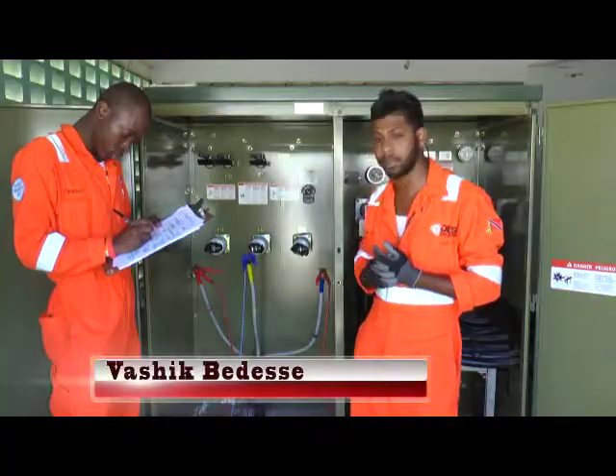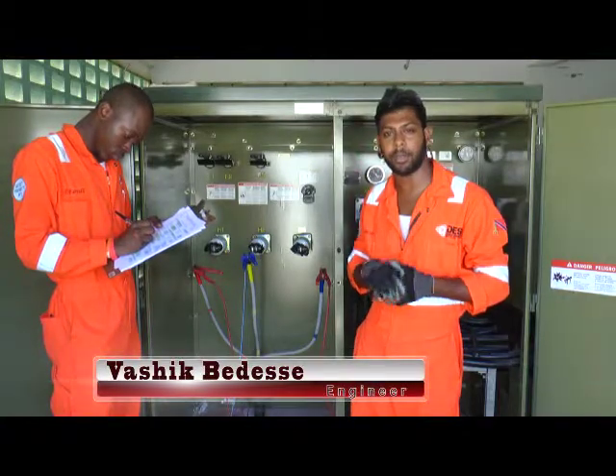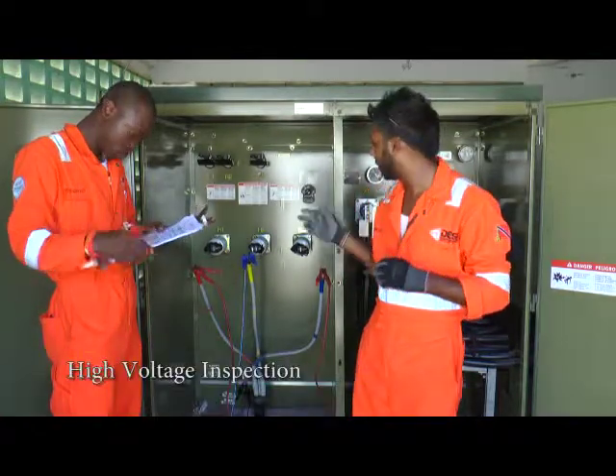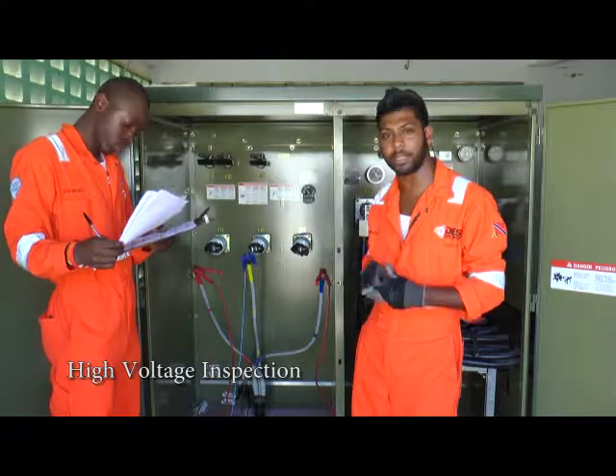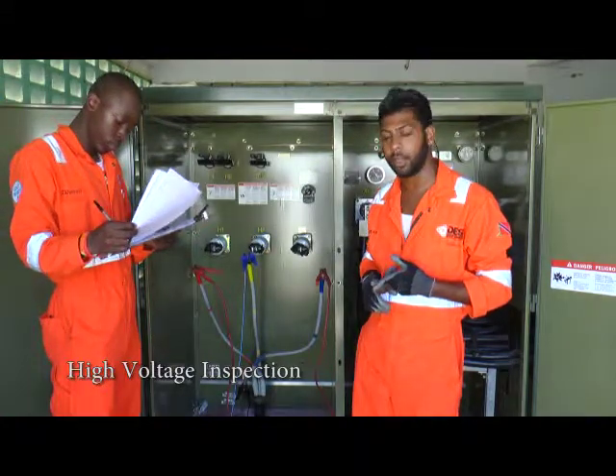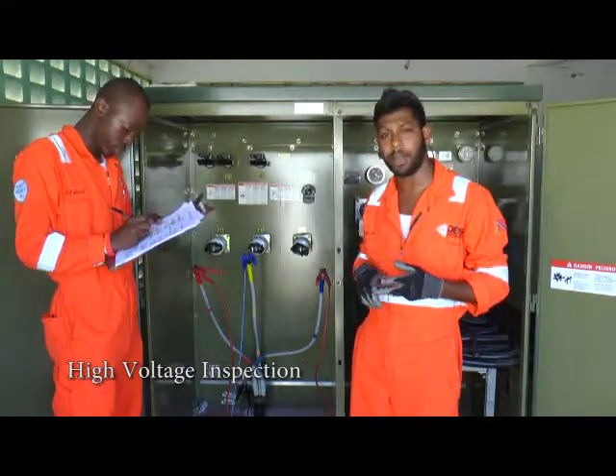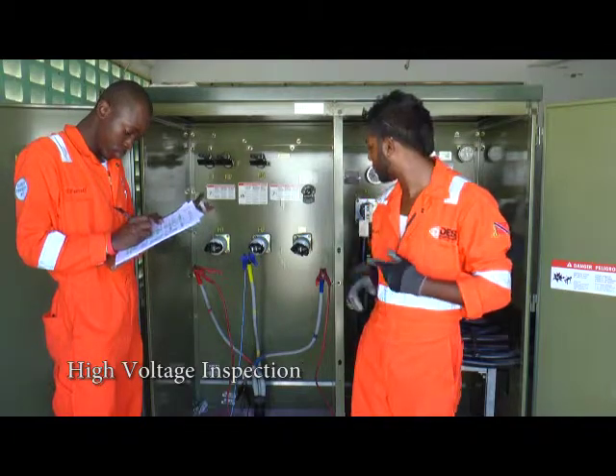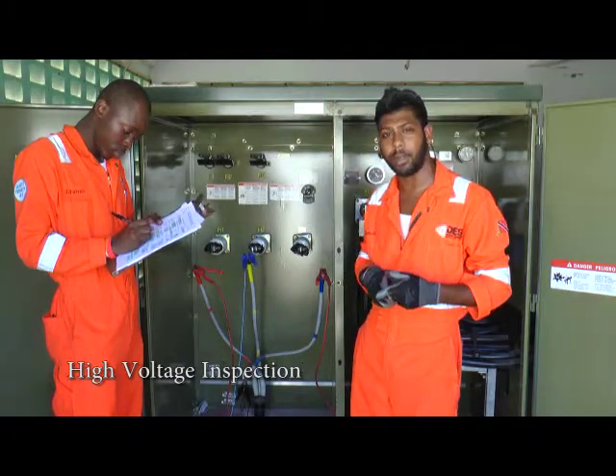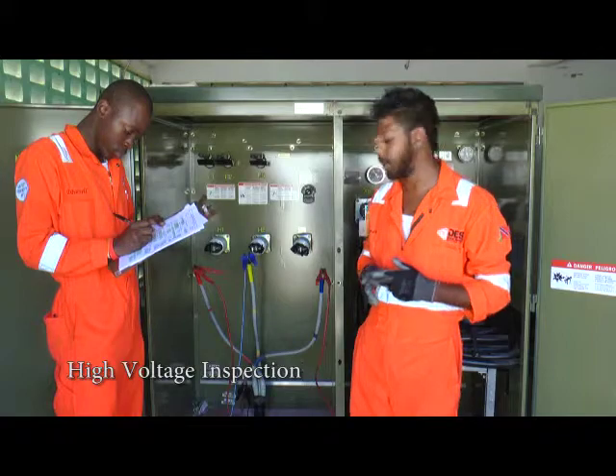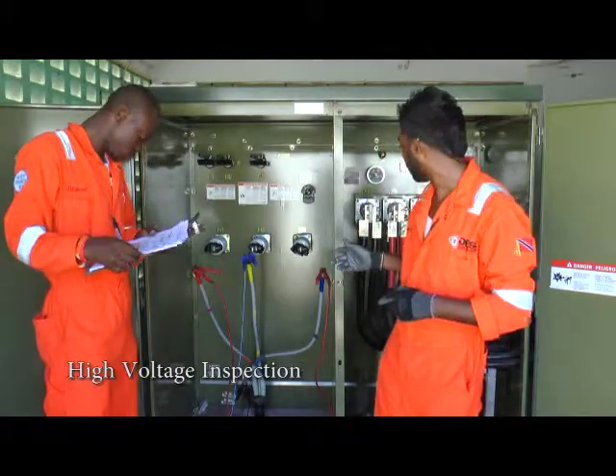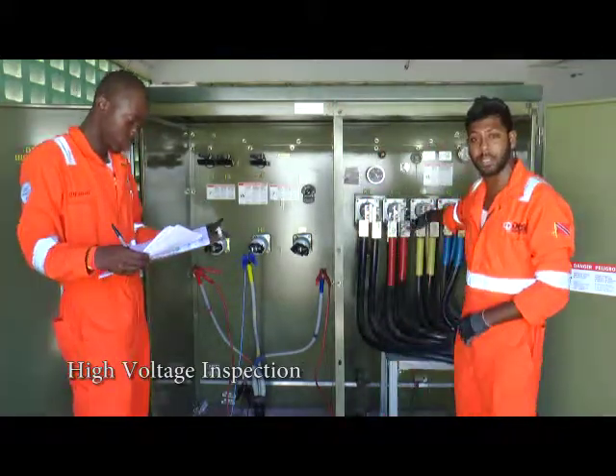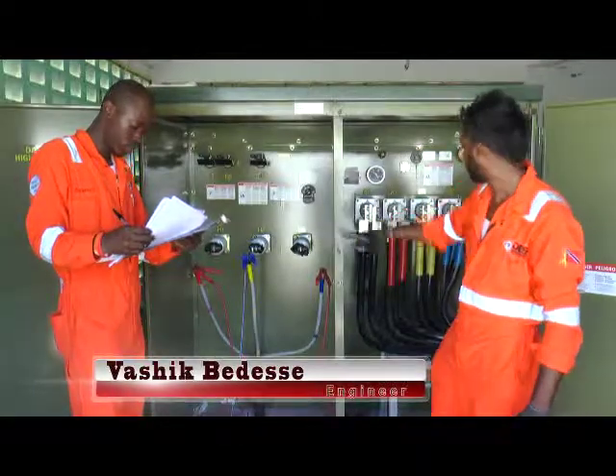We conducted testing at Lowlands Mall, Tobago. Well, what we did here was the transformer. We did an insulation resistance on the transformer, and we took an oil sample, and we did a ratio. The insulation resistance, we did it at 1,000 for a minute, and we did 5,000 for 10 minutes. Then we took the oil sample, and we disconnected the LV cables firstly to begin, and the HV cables, and we did the insulation resistance, as I said.